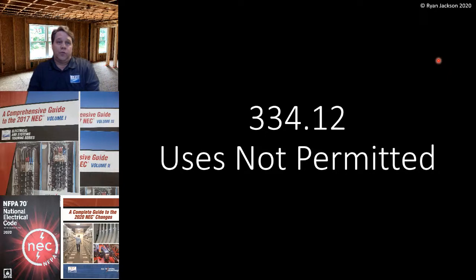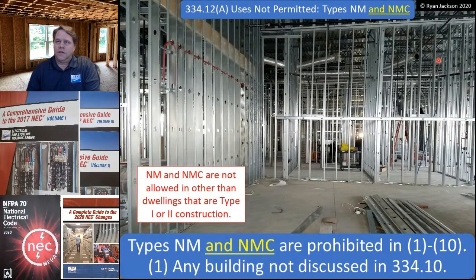Getting into 334.12, uses not permitted. And again, I want to reemphasize, I'm not going to spend much time on NMC cable. I just don't see the value in it. Uses not permitted, type NM and NMC. Okay, number one, we kind of already said this. Type NM and NMC are prohibited as follows in items 1 through 10. Number one, you cannot use, so read this carefully, you cannot use NM cable in any building that's not covered in 334.10. So, okay, now we're going back to type of construction.